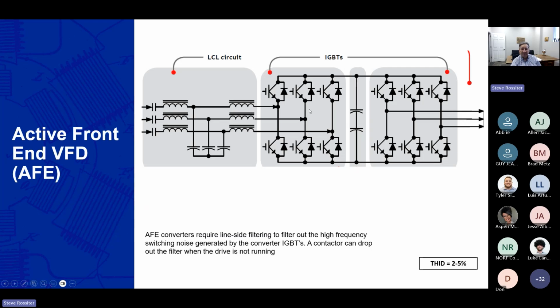It could be regenerating back onto the line. It could be improving power factor. You can do a lot of things with control. You've obviously complicated things quite a bit, but there are now more and more active front end variable frequency drives. Still fairly expensive, but there's certainly a place for them. The reason that they get expensive is because you almost always have to have an LCL circuit. So you still get back to having a pretty significant set of reactors and capacitors to get rid of now the high order switching frequencies.